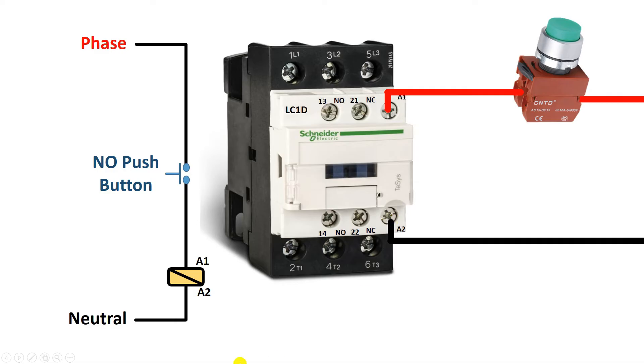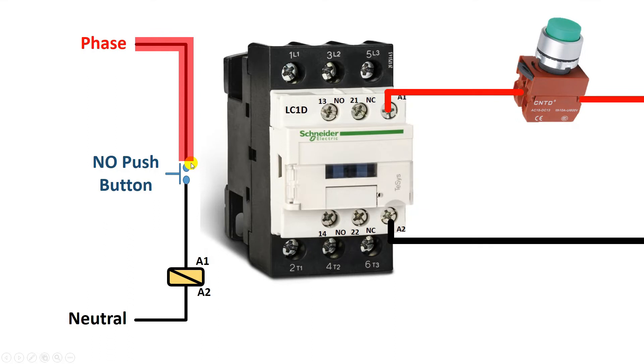At A2 terminal, neutral power supply is connected. Now at A1 terminal, phase supply is coming. In between, a NO push button is connected. By using the NO push button, this phase supply cannot reach the contactor because the circuit is in open condition. If you turn on the power supply, it will flow only up to this point and cannot go further. But when you press this push button, power supply will continuously flow to the contactor. And since the contactor is already getting neutral power supply, your contactor will turn on.